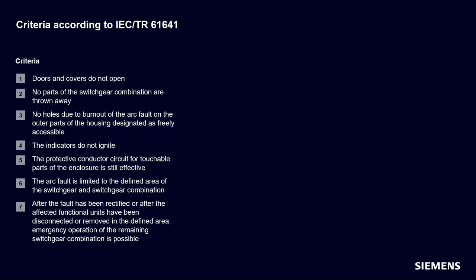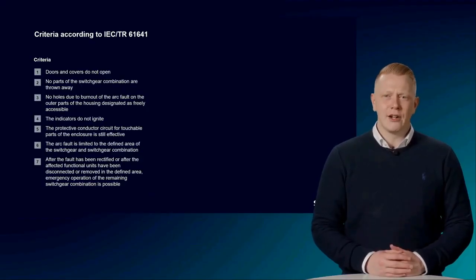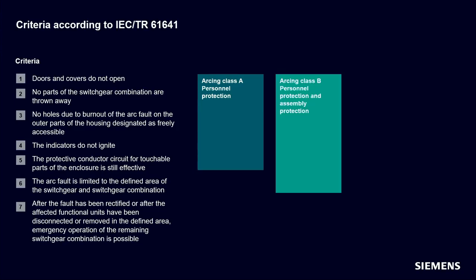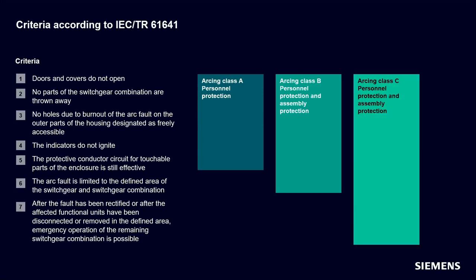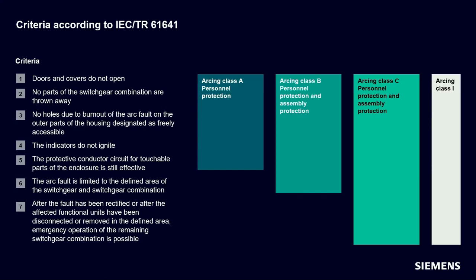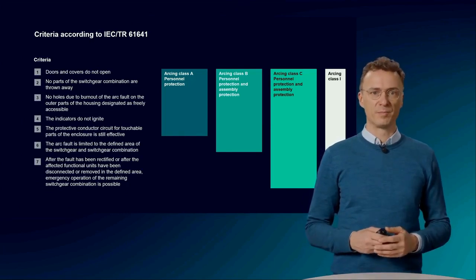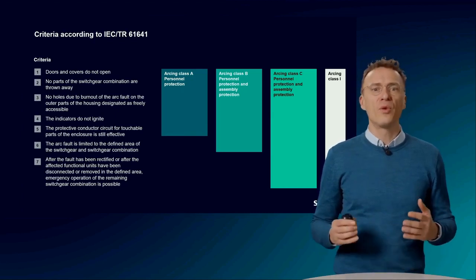Four so-called arcing classes are defined in the technical report. Arcing class A achieves personal protection under arcing conditions by fulfilling Criteria 1 to 5. Arcing class B corresponds to a switchgear assembly with personal and system protection, meeting Criteria 1 to 6 — limiting the impact to a certain area. In arcing class C, limited emergency operation as described in Criterion 7 is also possible. Last but not least, arcing class I is a switchgear assembly with a reduced risk of arc faults due to the sole use of arc-protected zones, such as insulation.